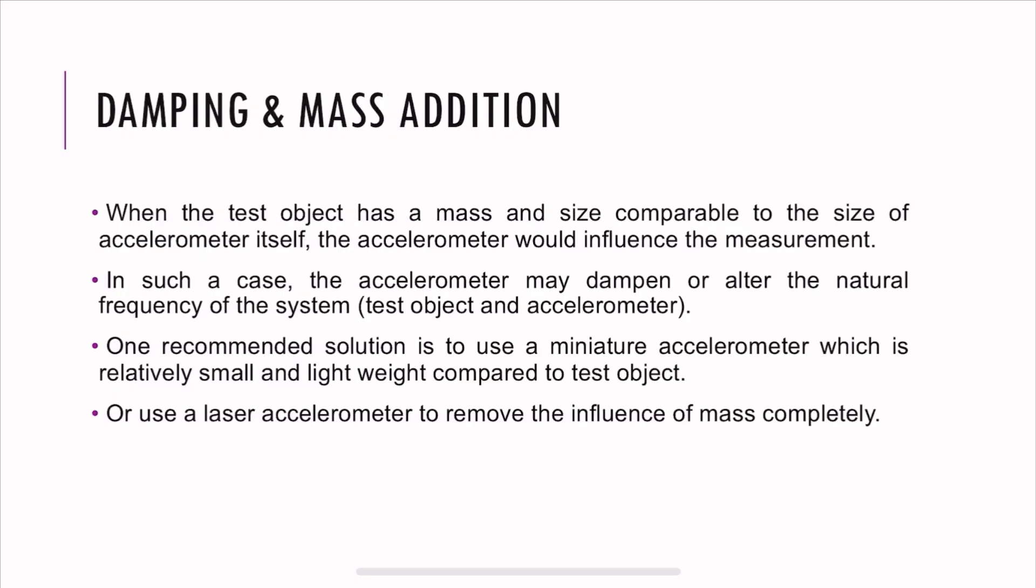There's one interesting thing, which is the damping and mass addition. What if you're mounting the accelerometer in the test structure, and that is influencing the structure's natural frequency? That should not be the case. When the test object has a mass and size comparable to the size of the accelerometer, the accelerometer is going to influence the measurement. If the test object is so small and the mass of the accelerometer is close to the test object itself, then it might as well change the spectrum.